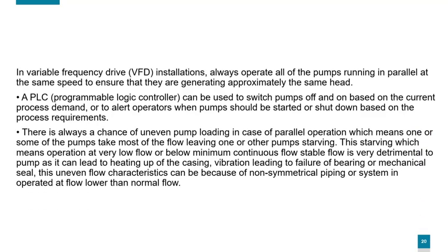There is always a chance of uneven pump loading in case of parallel operation, which means one or some of the pumps take most of the flow, leaving one or other pump starving. This starving, which means operating at very low flow or below minimum continuous stable flow, is very detrimental to the pump, as it can lead to heating up of the casing and vibration, leading to failure of bearing or mechanical seal. This uneven flow can be because of non-symmetrical piping or the system operating at flow lower than normal flow.